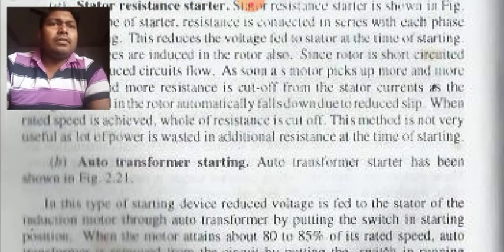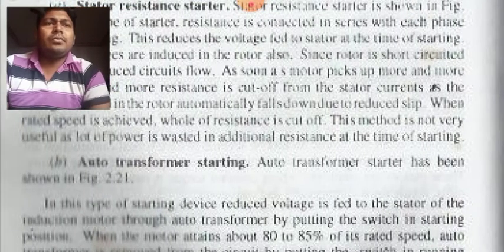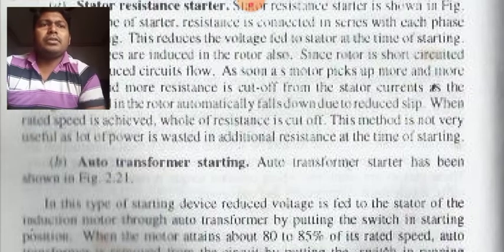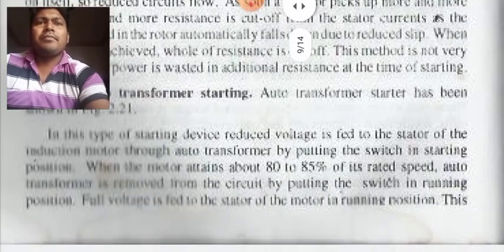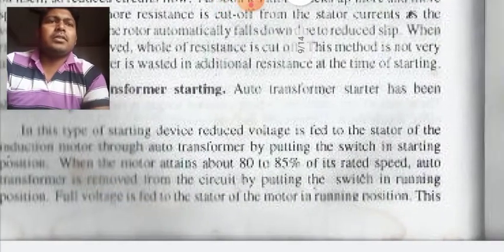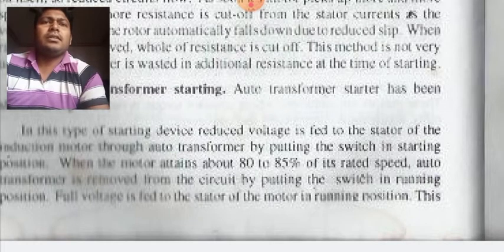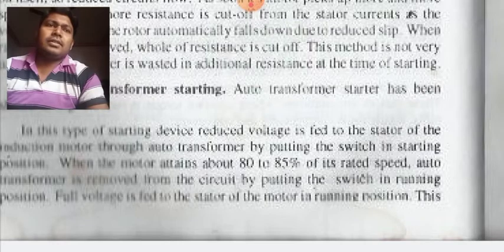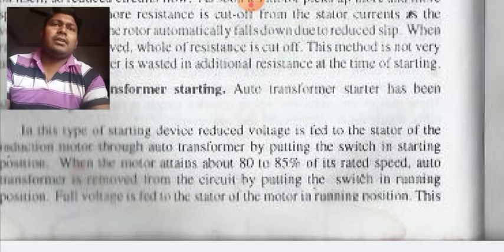In this type of starting device, reduced voltage is fed to the stator of the induction motor through the auto transformer by putting the switch in the starting position. When the motor attains about 80 to 85% of the rated speed, the auto transformer is removed from the circuit by putting the switch in the running position. Full voltage is fed to the stator of the motor in the running position.